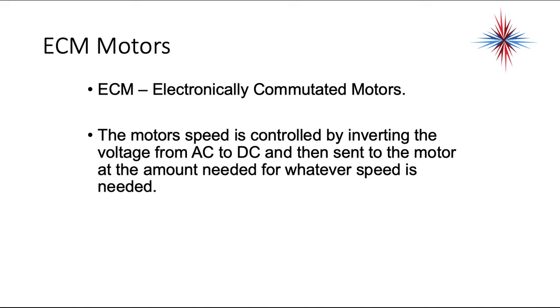With ECM motors, the motor speed is controlled by inverting the voltage from AC to DC and then sending it to the motor at the amount needed for whatever speed is required. With DC motors, we can very easily vary the speed by decreasing the voltage going to the motor. We're going to be seeing more and more ECM motors, and they bring a whole new breed of troubleshooting that's required, so we're going to talk more about those in another video.